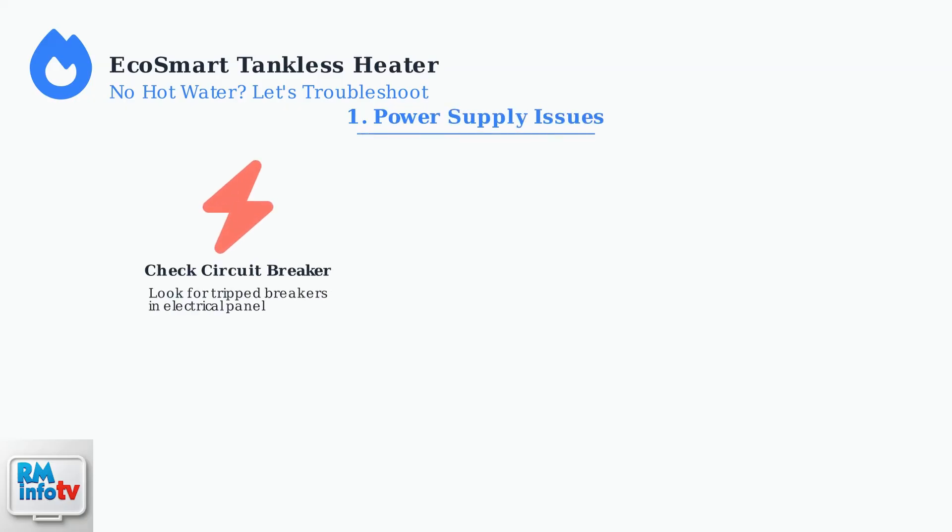First, check the electrical power supply. EcoSmart heaters require exactly 240 volts to operate properly. A tripped circuit breaker is the most common culprit.